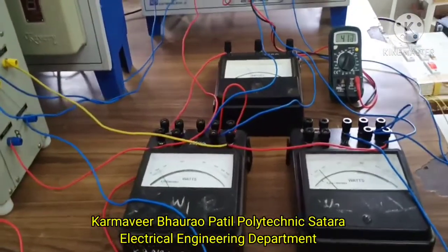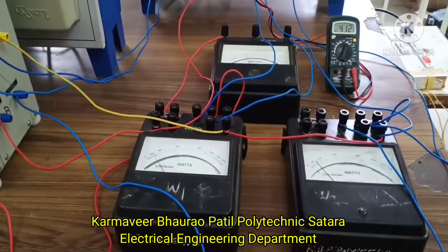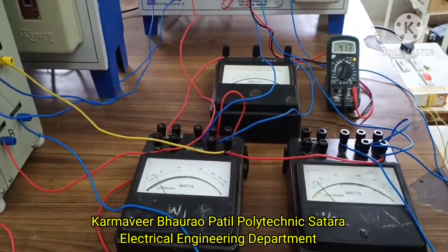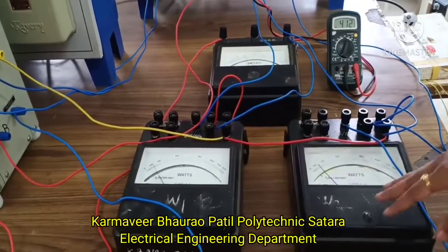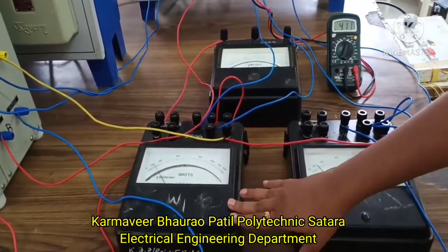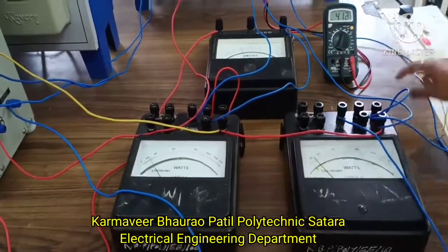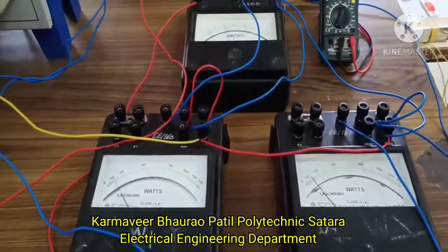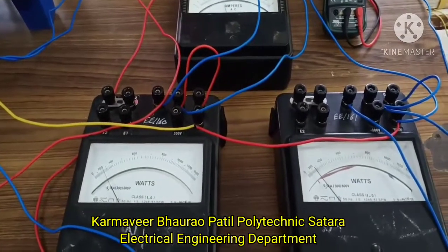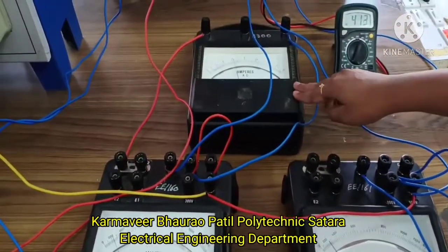So this will be the no load power, no load current and no load voltage. We are here applying no load voltage, so we will get the rated voltage V, the no load power W1 plus W2, and the no load current, that is I0.